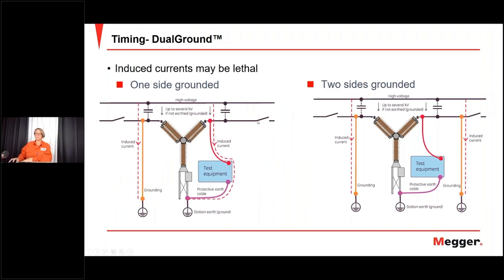So, we have opened the circuit. But when you have a parallel line, it works like a capacitor, a capacitance between the parts of a line which you have still in your circuit breaker circuit, and you will get an induced current down to the test equipment. When the breaker is closed, it will go this way. But as soon as you open the breaker, which you do during testing, this side's induced current from capacitive coupling will go through the instrument. But with two sides grounded, you will have a path and a safe environment where you work the whole time.